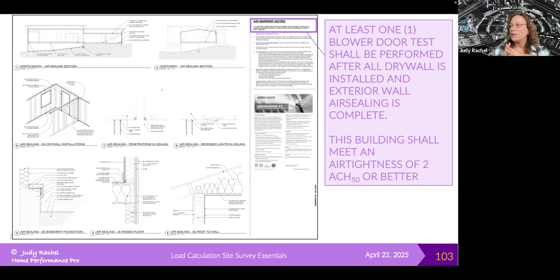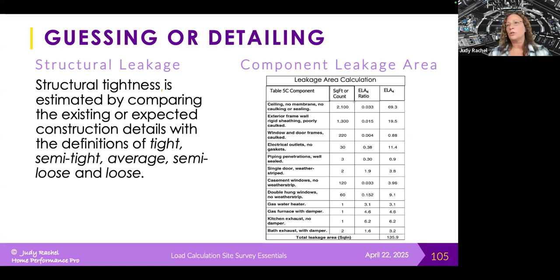So some of the collection challenges for infiltration is when you choose to not do a blower door test, that structural leakage estimation, which is, like I said, guessing this house is tight, this house is semi-tight. I feel like my ears pop when I walk in the door, so it must be tight. It's a total guess and it's completely inaccurate. The component area, like I said, is you're actually trying to figure out the square foot or count of all the different penetrations in the building. Just way too difficult and time consuming to bother with when you could just set a blower door up and get the actual infiltration rate.